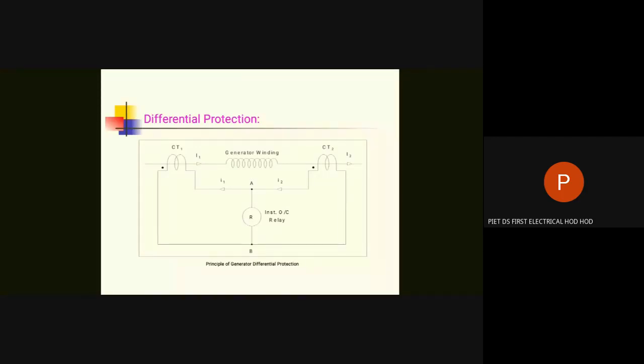So stator earth fault is a different kind of protection. This differential protection, the slide of which is against your screen, in that slide these CTs have a ratio of 10,000 by 5, and this protection is meant only for line to line or triple line fault. The winding that is shown is for a single phase. Such 3 phase windings are there. For 1 phase winding, the circuit is shown. The circuit is wired like this. You can see the dot on the CTs that shows the polarity. That means CTs have to be connected with correct polarity.